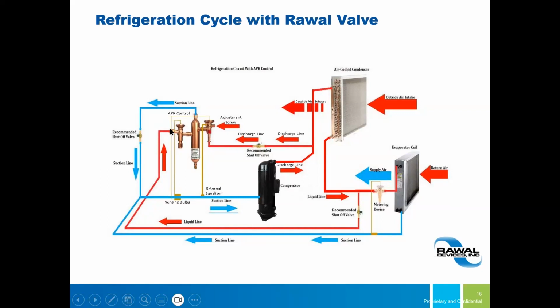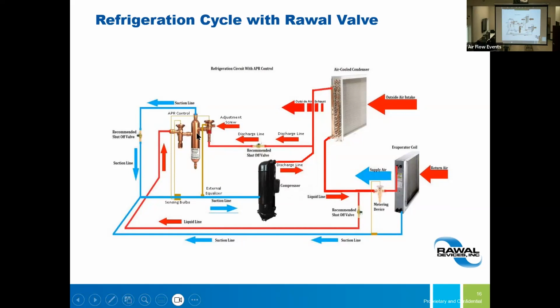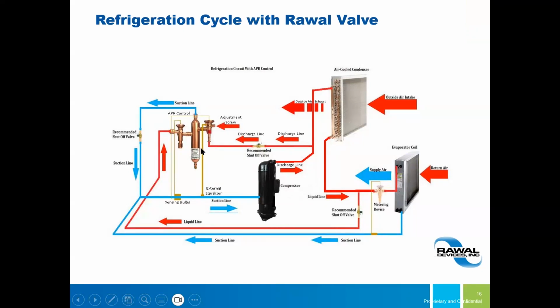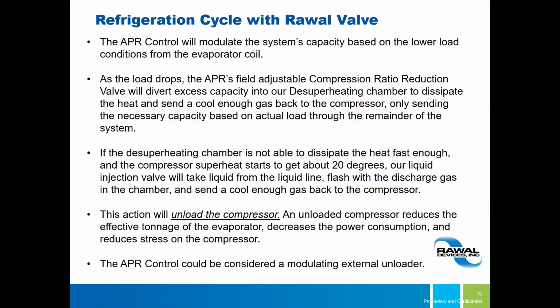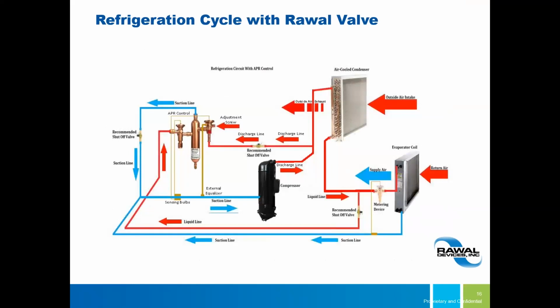And that's where it comes in. This is where your Rawal valve is, and that's where the liquid line injection comes into the system. And that's the de-superheater right here in the middle, so it runs through the de-superheater. What does a de-superheater do? Go back to the previous slide. It's there to dissipate your heat so that you can send cooler gas back to the compressor.